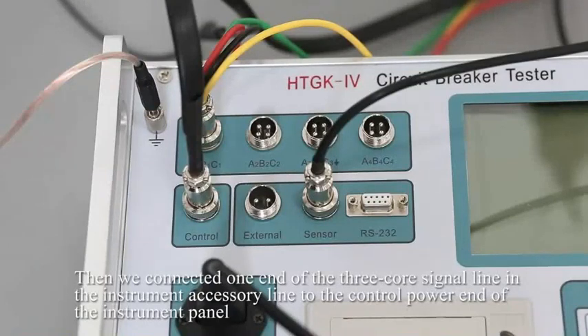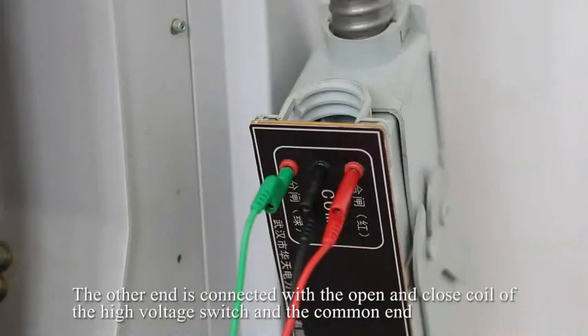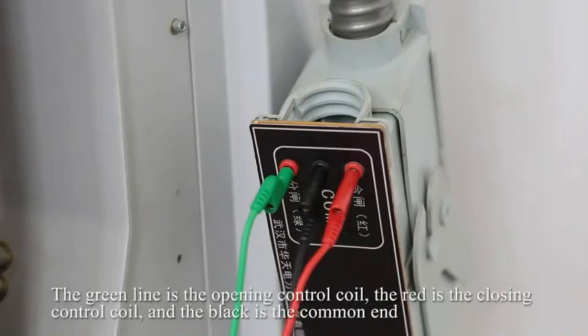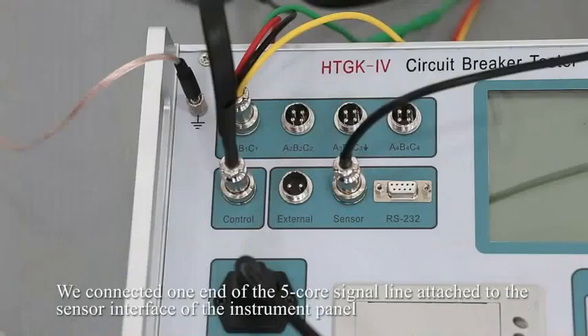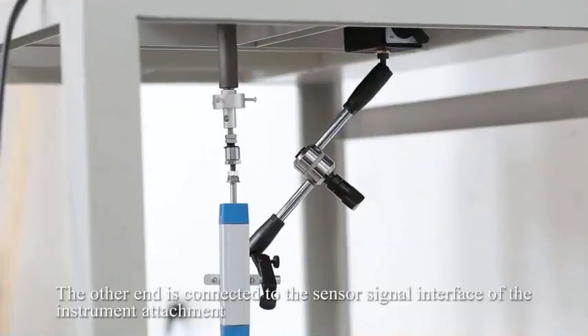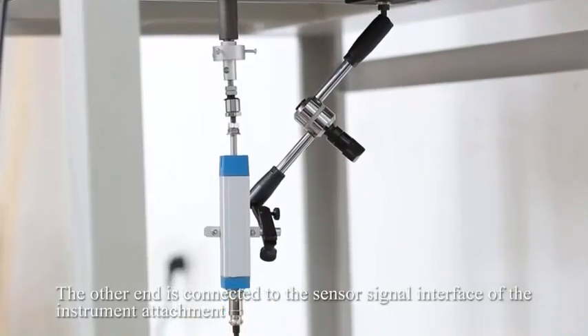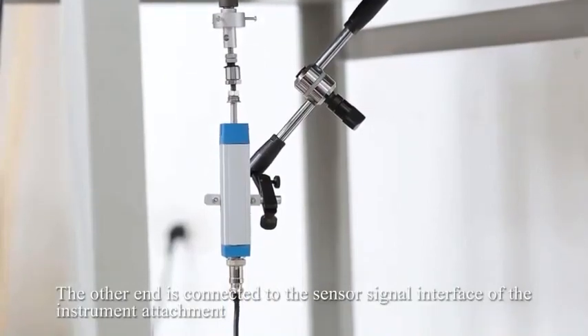Then we connect one end of the three-core signal line in the instrument accessories to the control power end of the instrument panel. The other end is connected with the open and close coils of the high voltage switch and the common end. The green line is the opening control coil, the red is the closing control coil, and the black is the common end. We connect one end of the 5-core signal line attached to the sensor interface of the instrument panel. The other end is connected to the sensor interface of the instrument attachment.